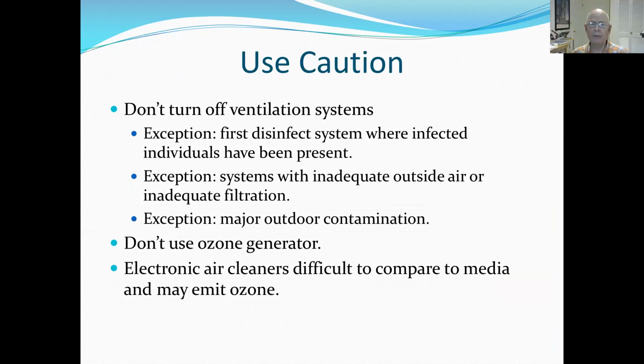We also say don't turn off your system. In the early days, some areas in China were saying turn off the system, or even maybe the WHO, I can't remember. Now, if you have a really poor system with no filtration and no outside air, and all it's doing is recirculating contaminated air in a small space, maybe. If you have had people infected, or you know somebody has already shown up with symptoms, maybe you get everybody out of there and you disinfect the system and don't run it then. Or if you had a wildfire event all of a sudden, or something outdoors, then you might shut it down.